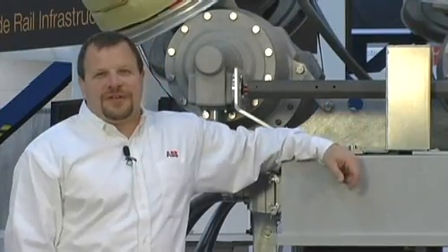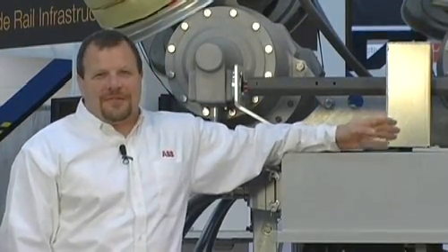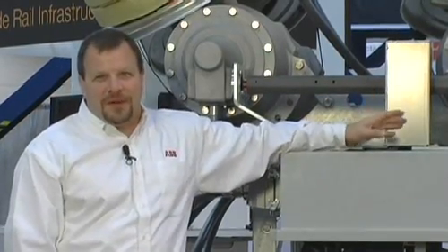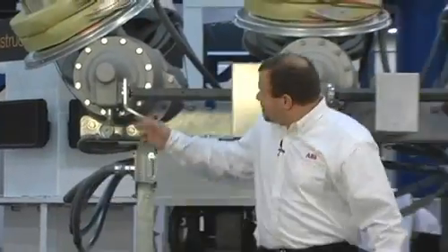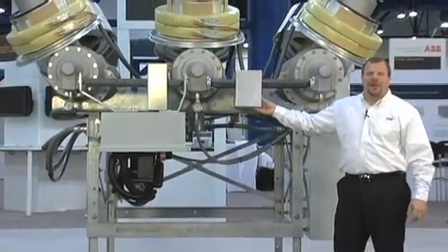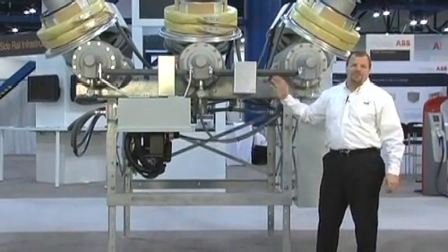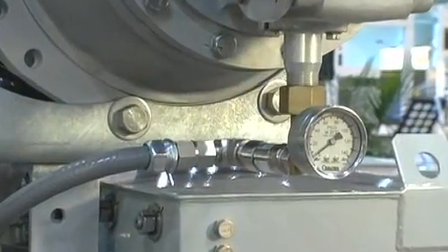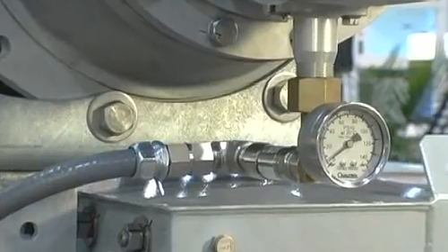One of the things that utilities users can do to reduce the amount of SF6 gas losses to dead tank breakers is reduce or eliminate the external plumbing on their breakers. Historically, the plumbing ties all 3 phases together, and it's done with brazed fittings or compression fittings, which break down over time and create leak points.